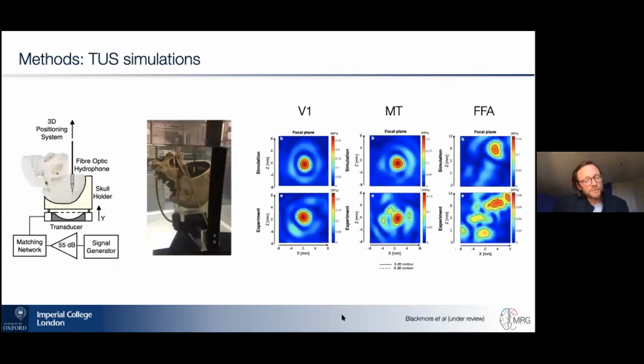We experimentally verified our modeling procedure using CT images of an ex vivo skull, and then compared the modeling results against the actual pressure fields measured by putting this skull in a water tank and using a fiber optic hydrophone. As shown here on the right, the simulations on the top for V1, MT, and FFA closely matched the measured pressures shown here on the bottom. Although for the deeper FFA region, there was greater field fragmentation than we had predicted in the model, perhaps related to reflections from the petrous temporal bone, but also the maximum pressures measured were lower than those modeled.